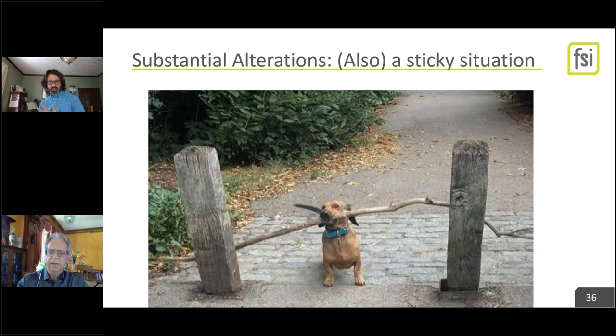Thank you. I can say I believe the rest of the requirements still exist. You get away from the insulation values out of that provision. There is an even further back provision, I think it's in section one, that if you're under 3.4 BTU per square foot, which is, let's be clear, like only passive houses can get there in actual occupied space. Even unoccupied, it's hard to get to that without insulating crazy out of the building. I think that one might get you out of a little more, but I'd have to go look at the Seattle specific to see if that one would get you gas. I don't think it would. I think it just impacts the envelope design. But yeah, we'll get to you. Just email me to remind me.